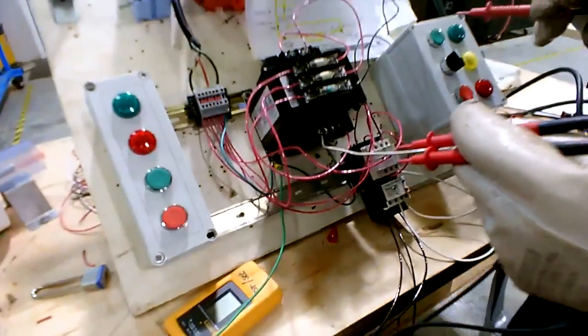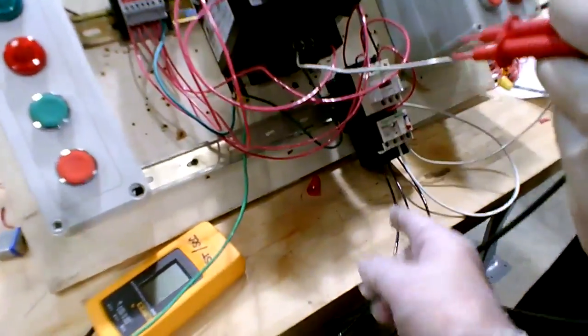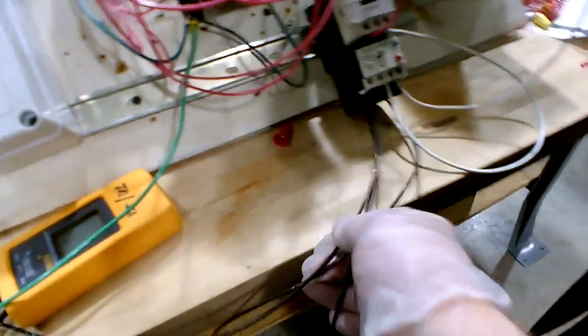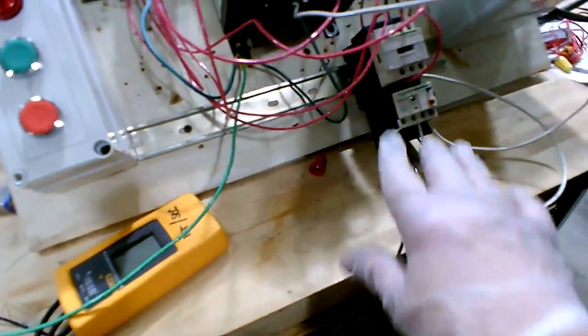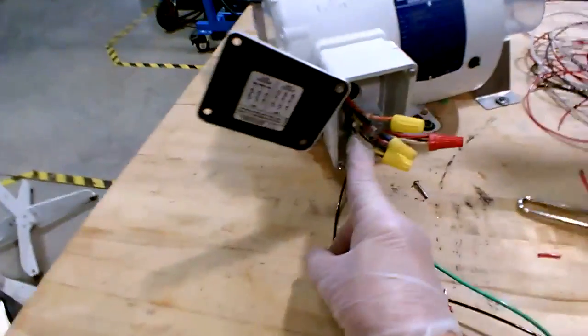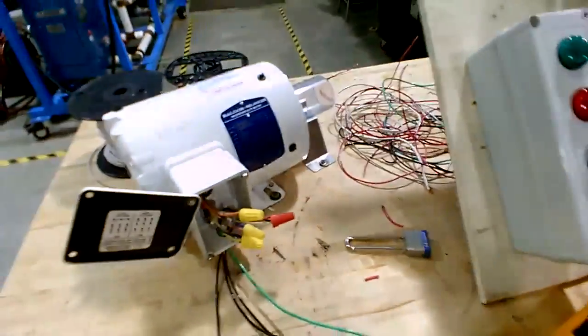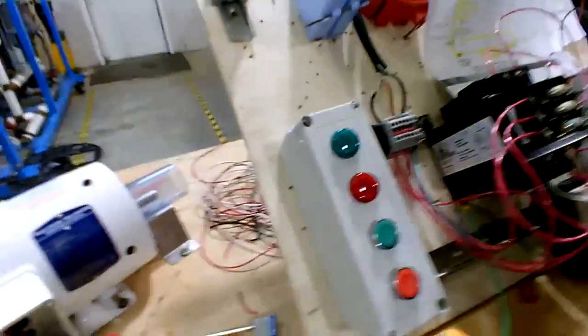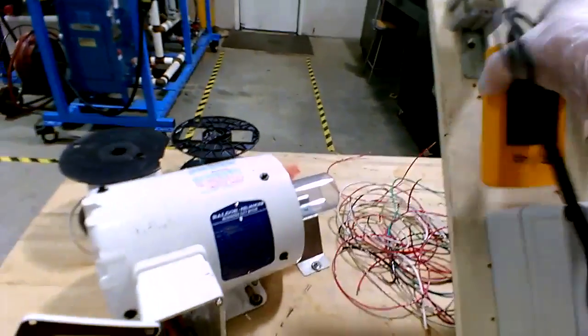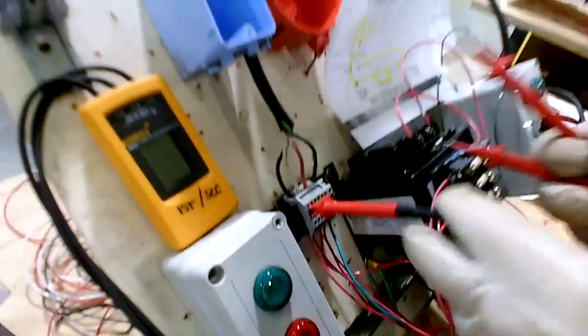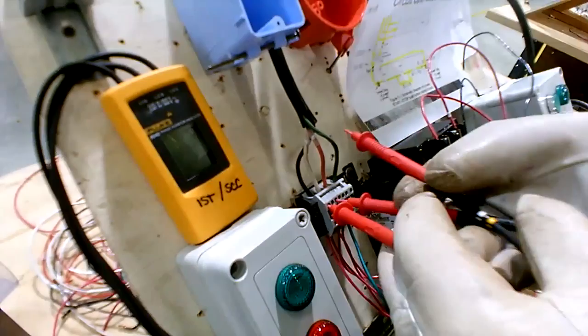Yeah, if you had done it up there, if you had done it at the top, it would show up at the bottom. But because the phase sequence is correct all the way to the bottom, if you change your sequence on the motor end, you won't see it with that meter unless you actually go on the motor end to read that. So if you go up here and put these in the wrong order on the strip, then you'll see it. It'll show you the opposite direction. Instead of going 1, 2, 3 with the plugs, just change it to some other order, and the meter will tell you that if you go in that sequence to the motor, the motor will go the other direction.